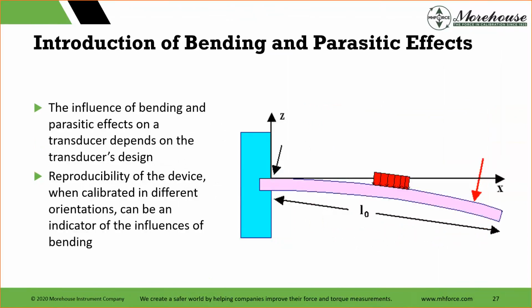So, and then we're talking of bending and parasitic effects. The influence of bending and parasitic effects on the transducer will be dependent on the design of the transducer. Not all transducers are made the same. However, the reproducibility of the device when calibrated in different orientations can often be a good indication of influence in bending. So you have that square drive, you put it in your machine, you put the arm on, you put weights on it, you get a number. That's probably all you're doing. If you're doing more than that, that's great.